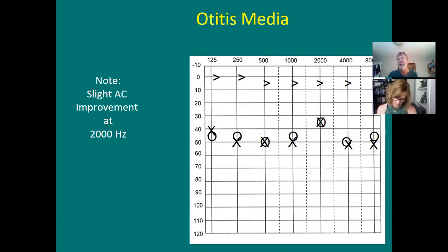In elderly people, you are losing cartilage in your outer ears. And when you lose cartilage, if you cover the ear with a headphone, like a circumaural headphone, you might collapse the ear canal, which causes a high frequency, that's unusual, a high frequency air bone gap. So you might see a high-frequency air bone gap with circumaural headphones in the elderly. The solution is to use insert headphones because it forces the canal open.